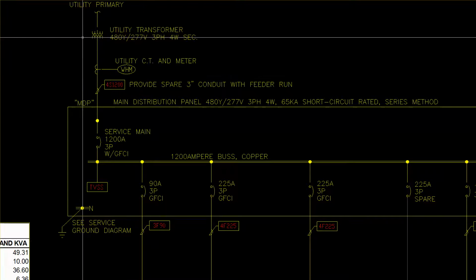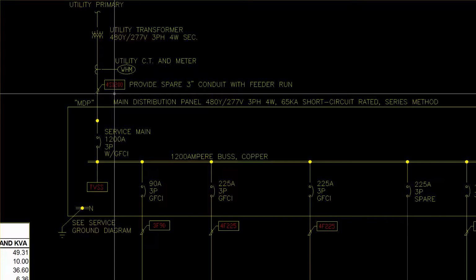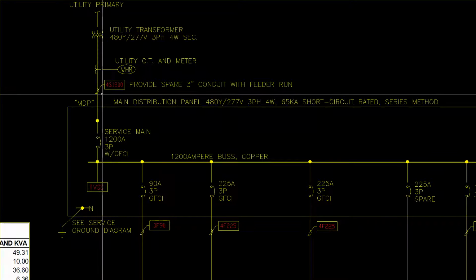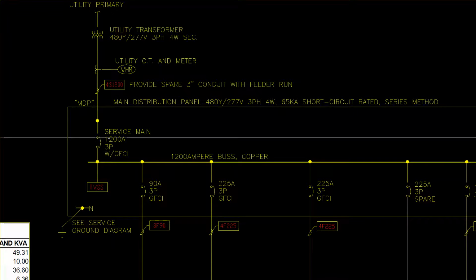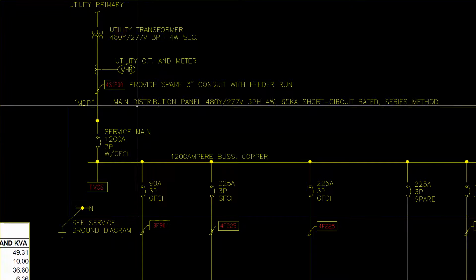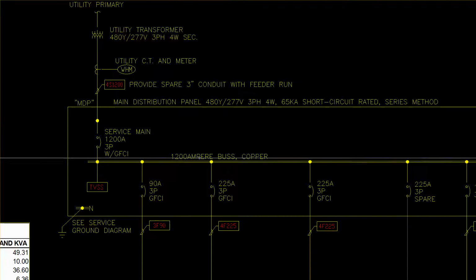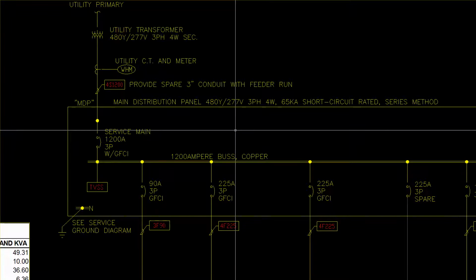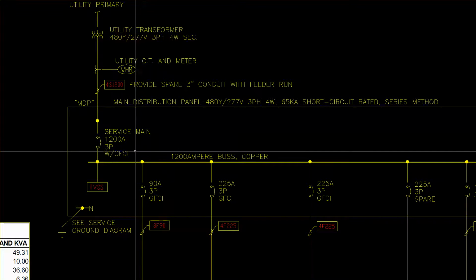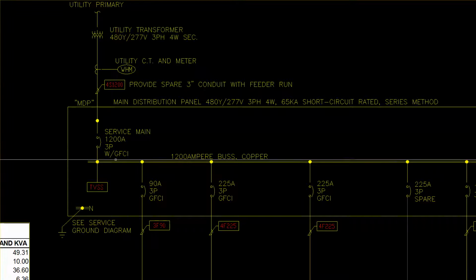See, here's the utility transformer. Here are, and what you'll see is tags. So this 4S1200, you'll see the 1200 amp main; the main distribution panel is also rated at 1200. We have a 1200 amp bus. This is going to give the contractor the ability to buy the correct piece here. And so that's what we're trying to accomplish there. This one's 1200 amps at 480 volts, and so code requires that to be GFCI protected. We also have TVSS on this one.